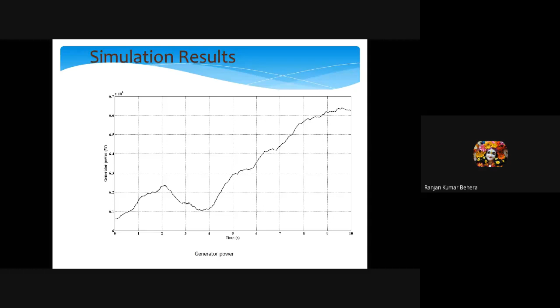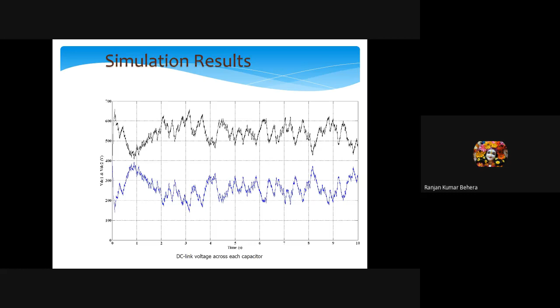Now if you see here, the DC link voltages are not actually constant and not balanced. There is an imbalance because inherently, as I told you, these voltages are unbalanced due to mechanical factors as well as different currents injected into your DC link capacitors. So we need to control this from the input side, not from the generator side. From the grid side you can control this, or you can use some kind of chopper circuit where the chopper can force the DC link capacitor to charge and discharge immediately, so that you can maintain constant and balanced voltage.